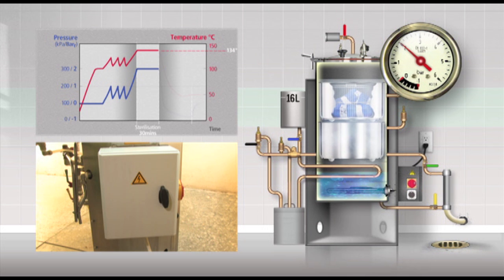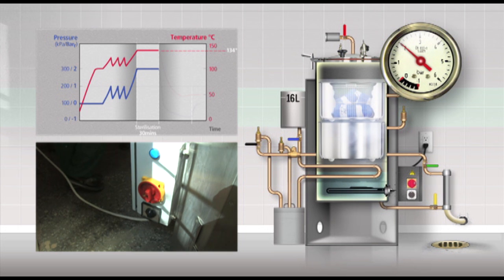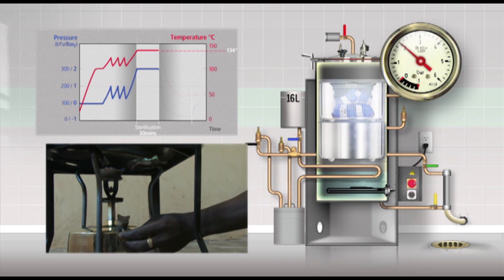After 30 minutes you can then stop heating. With electrical heating, switch off the power by putting the power switch in position zero. In the case of kerosene heating, put out the flame by opening the air release valve on the burner so that the pressure will drop and the flame will go out.